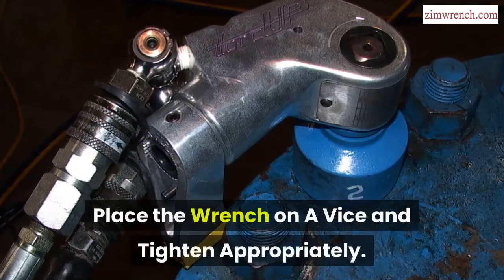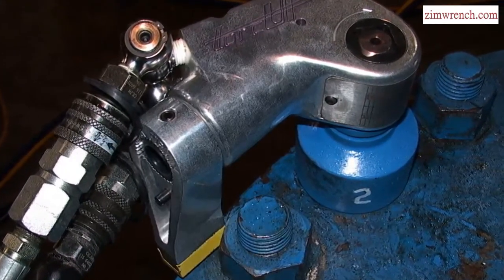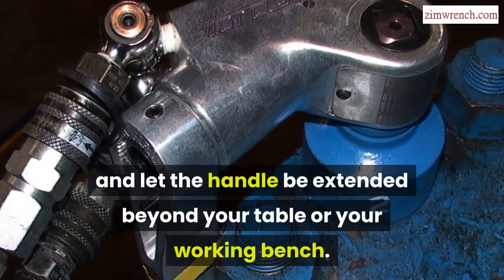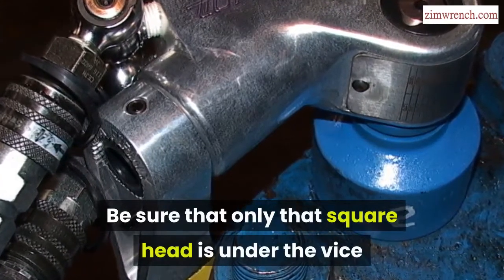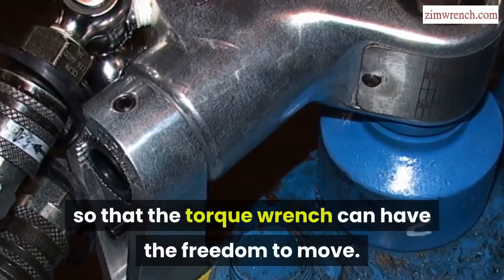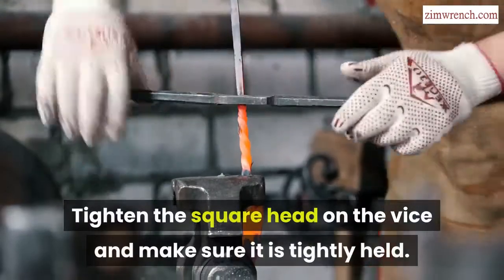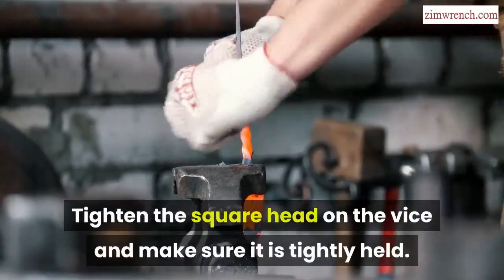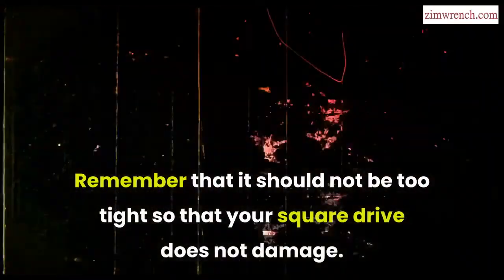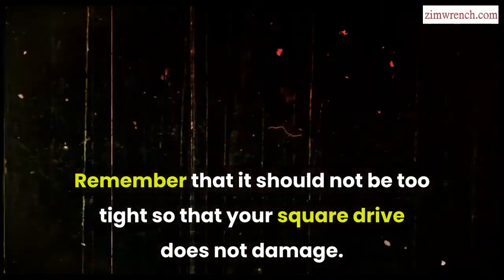Place the wrench on a vise and tighten appropriately. Put the square drive only on the vise and let the handle extend beyond your table or your working bench. Be sure that only that square head is under the vise so that the torque wrench can have the freedom to move. Tighten the square head on the vise and make sure it is tightly held. Remember that it should not be too tight so that your square drive does not get damaged.